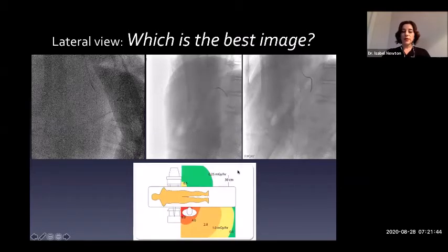The important thing, though, is to remember that the closer you are to the source, the higher the dose. And so you can get a lateral image by swinging your C-arm in either direction. So why ever would you swing it so that the source is closer to you? Because look, you're in the red zone. You could be over here. So just swing it in the opposite direction. Put the detector on your side. I hope I've helped to dispel any myths that the closer you are to the detector, or if you have the source pointing at you, that you would somehow have greater dose.